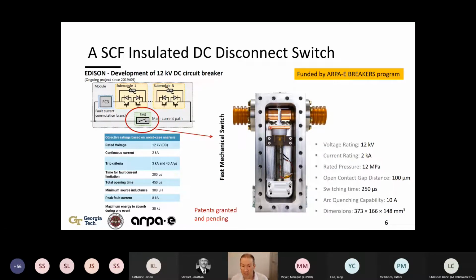This is why we're currently using this in a number of projects, most importantly our Edison hybrid DC circuit breaker. This is another project that we have with ARPA-E. We are about halfway into the project. It started 2 years ago, and we have another 1.5 years in front of us. We've designed, built, and are currently in the testing phase of this disconnect switch, rated 12 kilovolt DC, 2000 amps. It uses carbon dioxide or mixtures of carbon dioxide with other materials. I'll come back to this later.